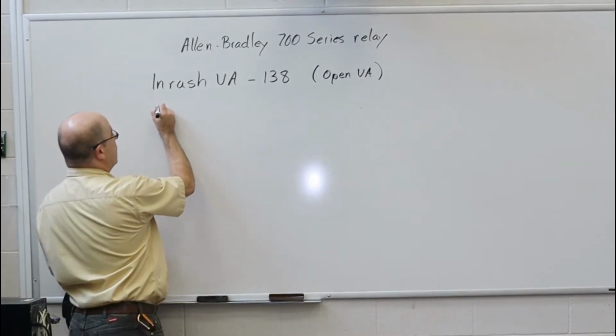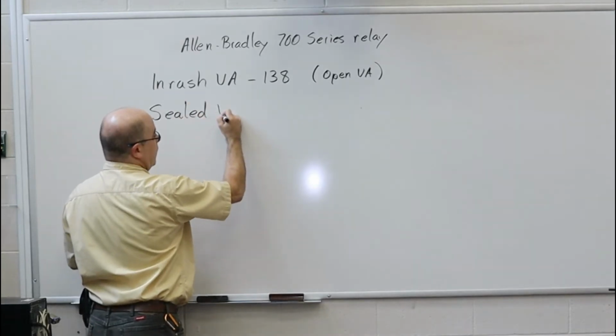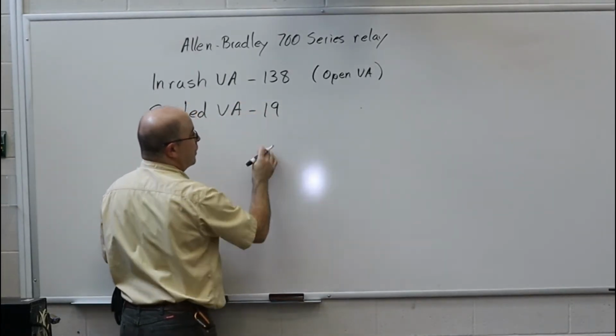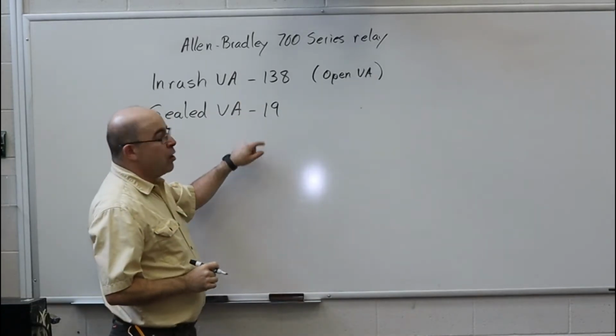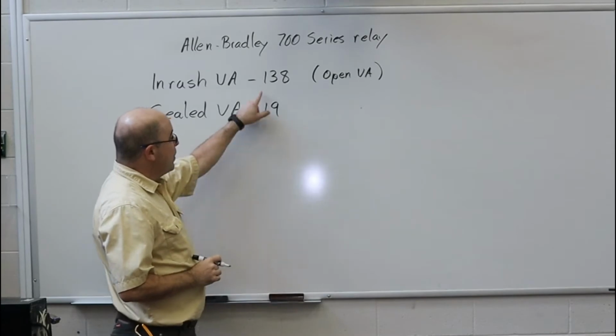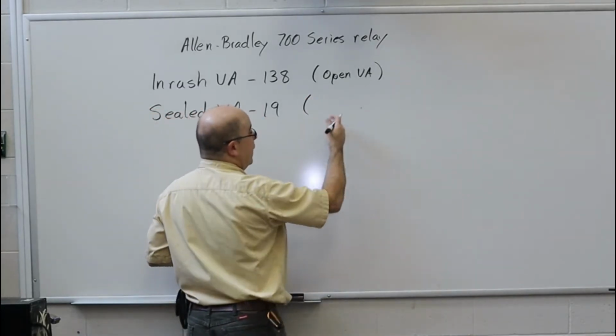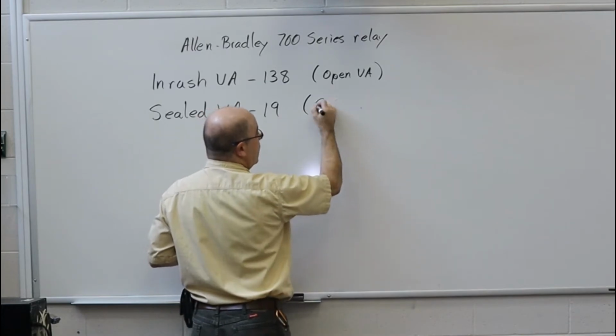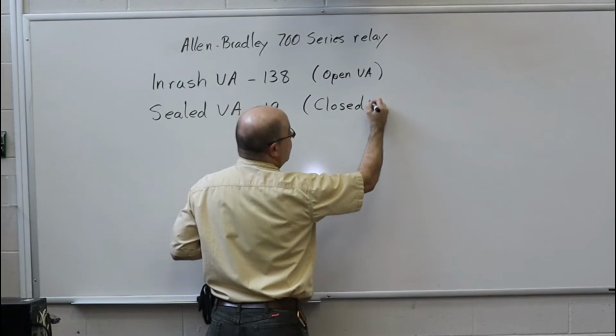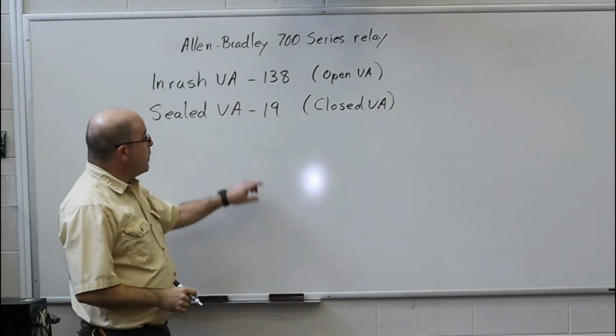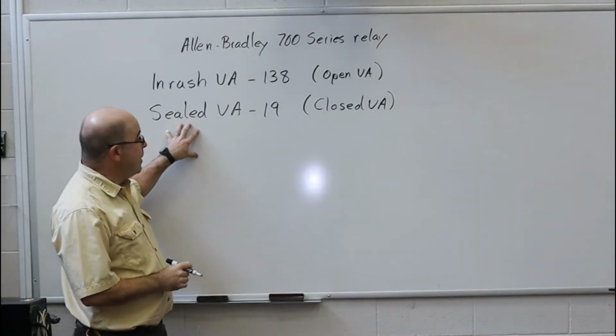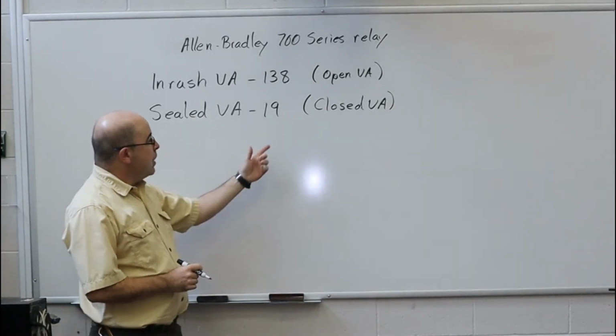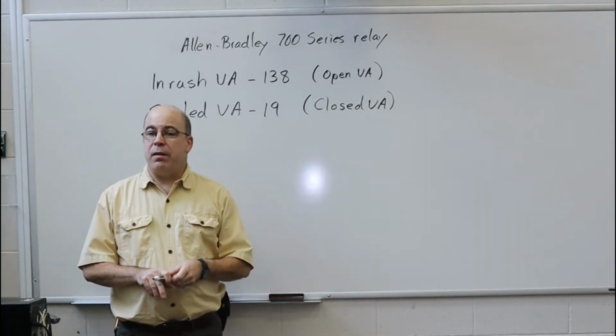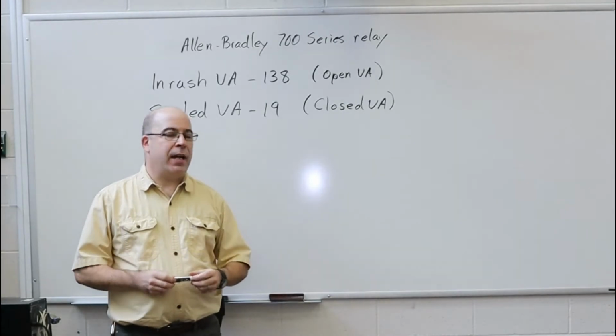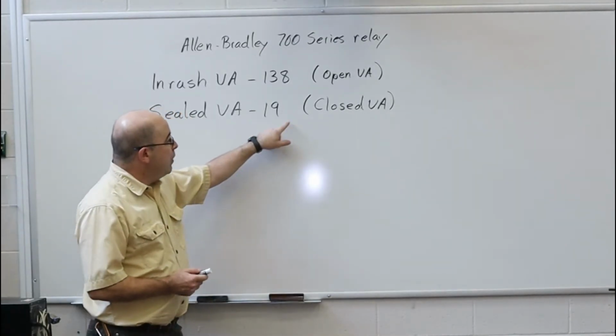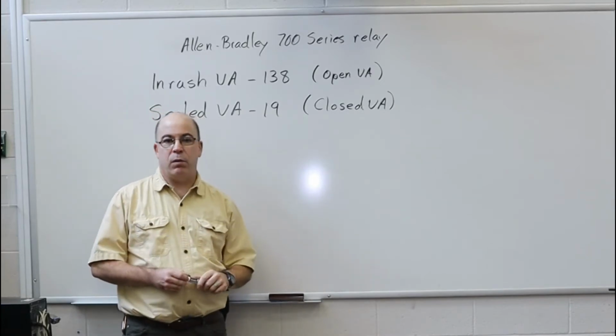Now, we've got what we call the sealed VA, and that came in at 19 VA. Quite a big contrast in the values, and actually it's about 6 times less. And again, if this was the open VA, certain manufacturers will describe this as the closed VA, meaning that once the armature has pulled in because the coil of a relay is energized, the magnetic flux has grown exponentially due to the fact that the coil is now an iron core inductor. And as such, it does not require the same value of apparent power to maintain a closed state.